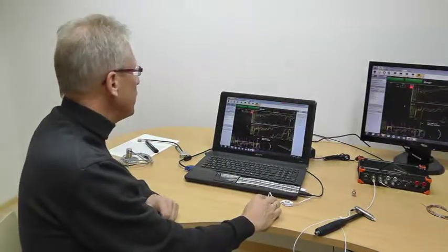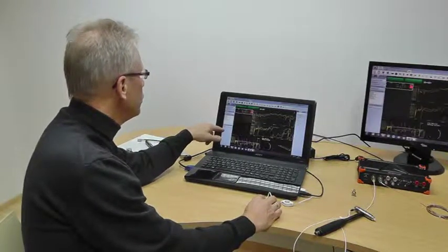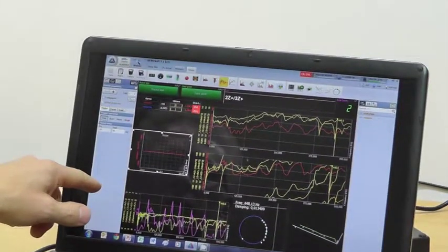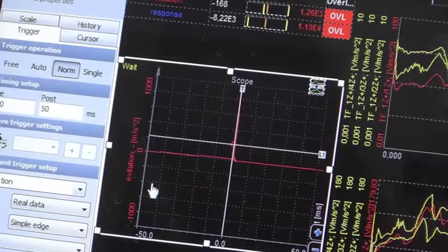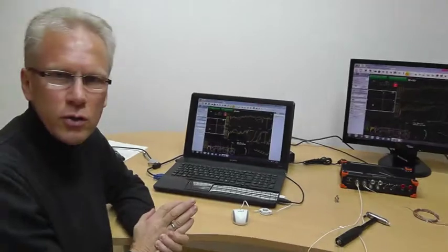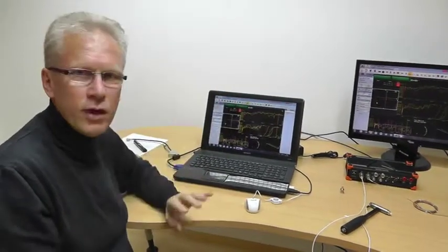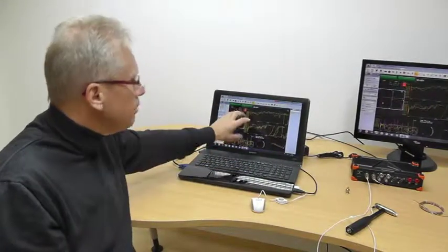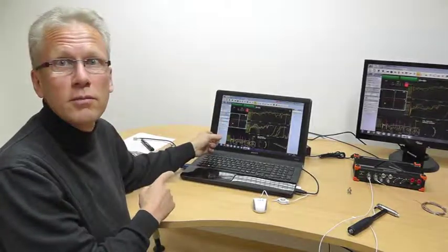One other thing I often like to add is maybe a scope to show you a little bit of the excitation, as I did before. When you hit the hammer, you can see whether the hit is okay or not. You can add that on. But the nice function you can see here is that the basic FRF, the difficult things with these buttons, all this stuff, is done automatically. You may modify it if you want. Your customer will like that for sure.